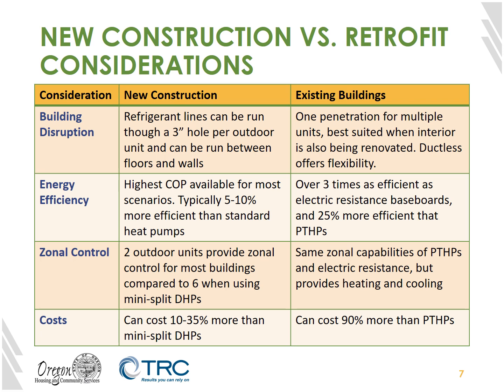when it's not being taken up with large HVAC chases. For an existing building, again, one penetration versus multiple penetrations is a large benefit when renovating or retrofitting a building. It is best suited when we're also going to be doing some renovation and retrofitting on the interior. That way, that will allow us to open ceilings, open walls, etc., to run these refrigerant lines and liquid lines throughout the building. That is something that we want to be able to consider if we're looking at a renovation or retrofit that's not going to have much disruption on the interior of the building. We have to ask ourselves if the VRF system is the correct or best approach. I might say that the integrity of the exterior of the building is of such high value that when I'm forced to look at a decision like this, I'm going to strongly weigh that 1 or 2 external penetrations versus having to do some renovation to the interior of the building.